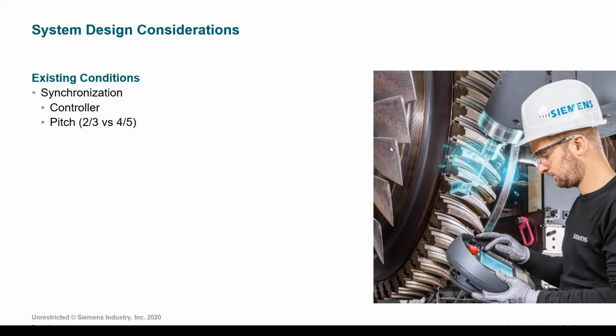Briefly, on existing conditions, it's important to make sure that the controller, which is integral to the generator, is sufficient for the paralleling capability, and that the generators also have the same pitch, whether it's 2/3 or 4/5.